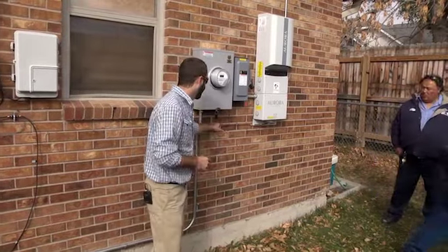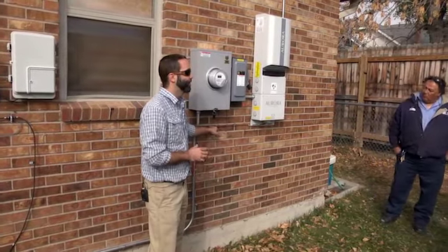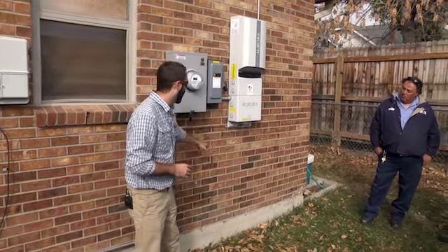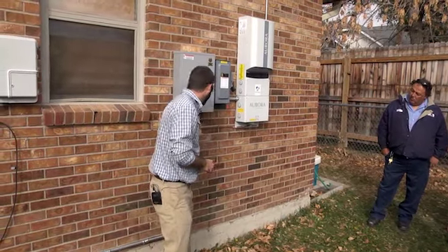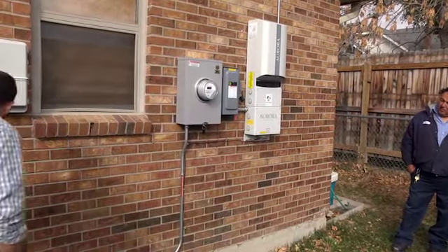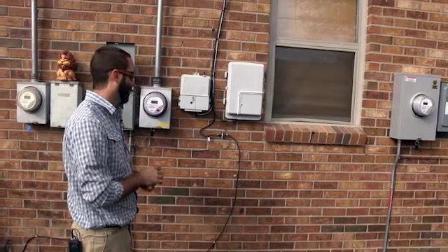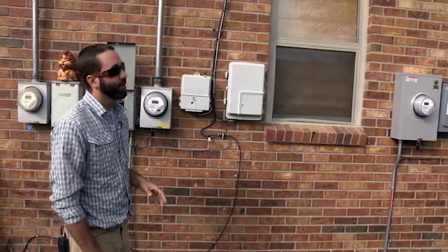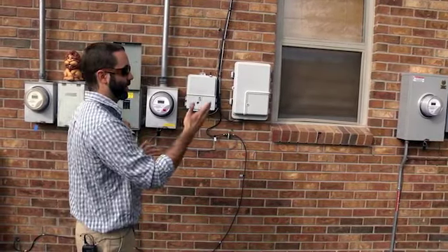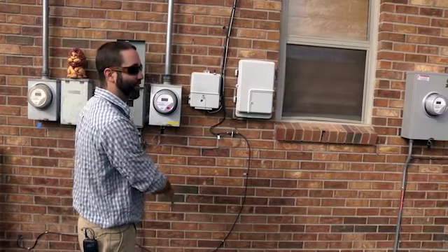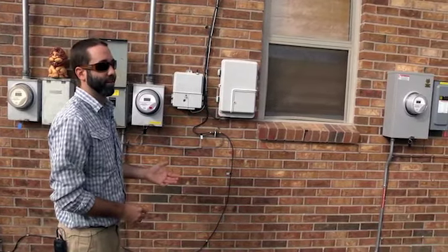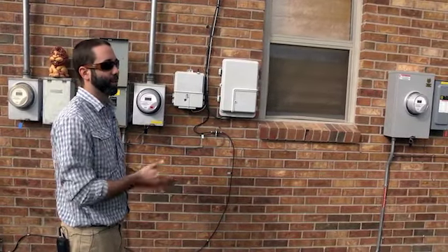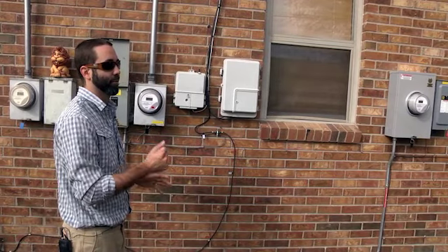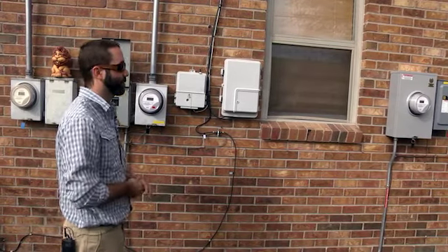The question was, how is the system grounded? Each one of these systems, both the inverter and the AC disconnect, are grounded back to the original ground rod. This is a grounding electrode conductor, a conductor that connects the system to the grounding electrode. There's also an equipment grounding conductor that runs through all the conduits and everything, but the grounding electrode conductor is a much more direct path to ground. So if that's missing, we do need to replace it.